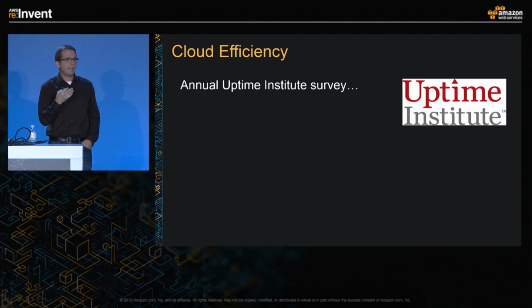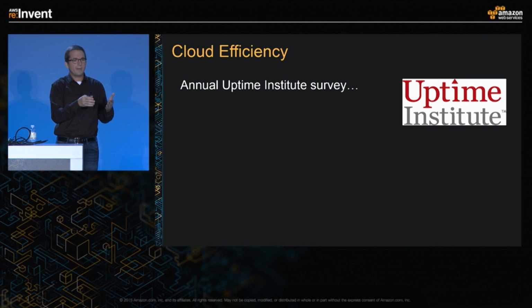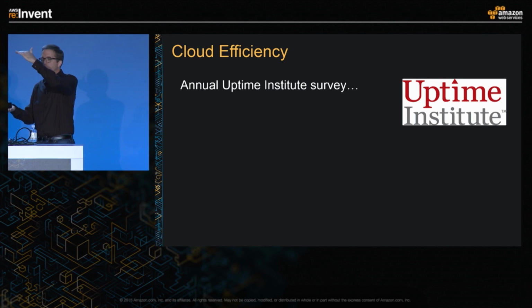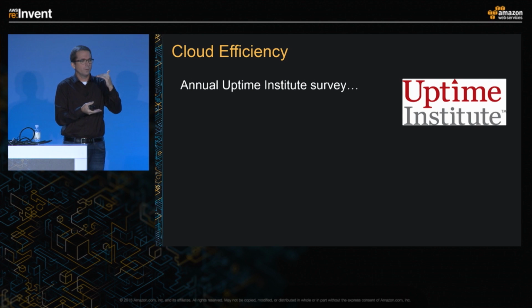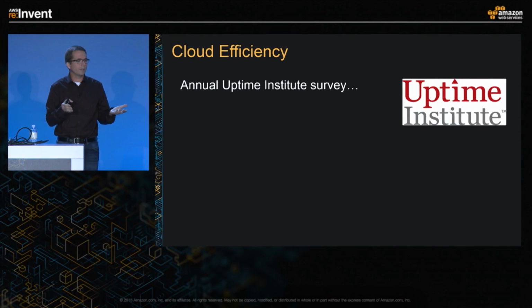Whereas if you had a 1.9, that meant that 1.9 units of power were pulled to support 1 unit of critical compute. Now, that 0.9, you might wonder where it goes. Turns out it's used by chillers, air handlers, or is simply wasted in the distribution process. So again, the closer to 1 you get, the better you are.